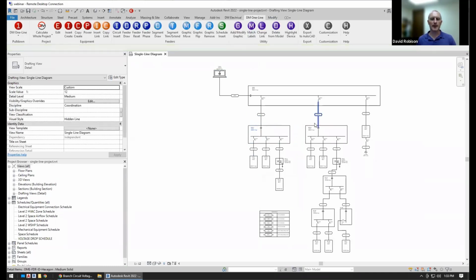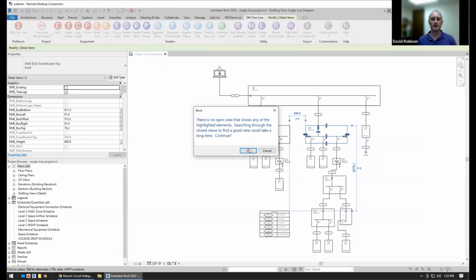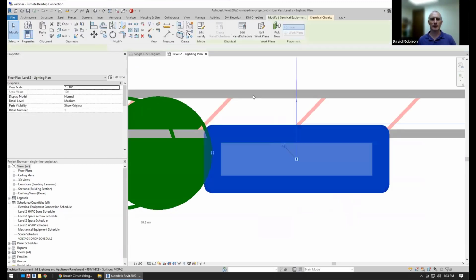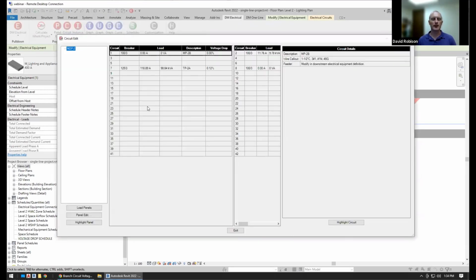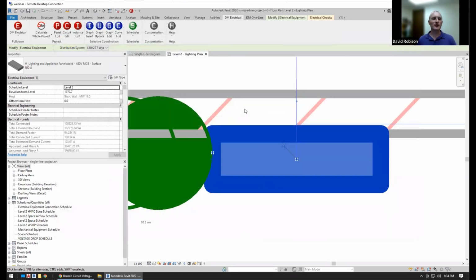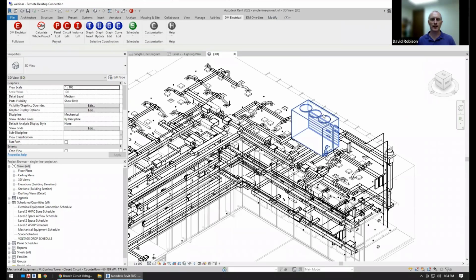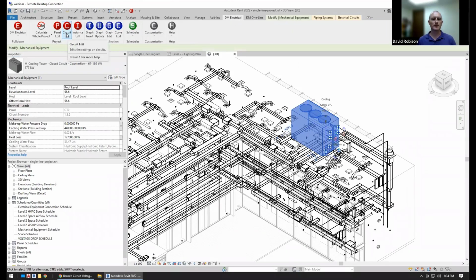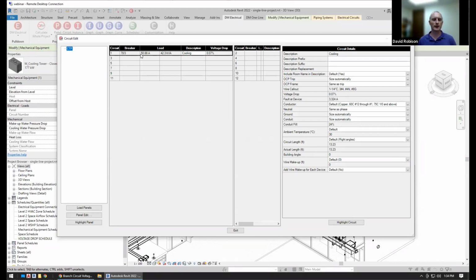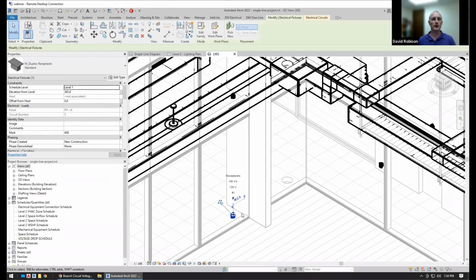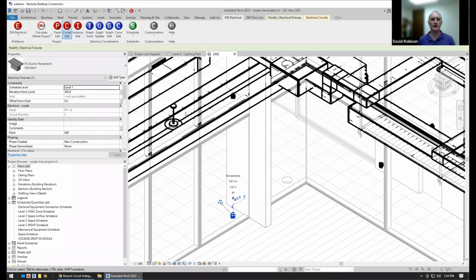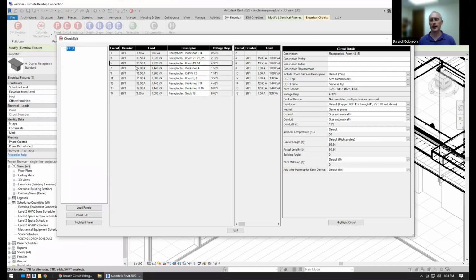If we go find a panel on the plan view, so we've got this panel here in the plan view, and the same thing, if we have that selected and we run the circuit edit command, it's going to select that panel for us. If you select a device, it's actually going to open up that specific circuit for you. So if I go to my 3D view and I select this cooling tower and we run the circuit edit command, it's going to open up that panel and then that circuit for us. It's not as interesting here because there's only one circuit on that panel. Say I go to one of these receptacles and who knows what circuit that's on. If we run DM electrical and we run the circuit command, it's going to pull up, okay, it's on PP1A, circuit 5. And now we can start working on that circuit, making any changes that you need to do. So you can get to that circuit just by selecting the device and running the circuit edit command.